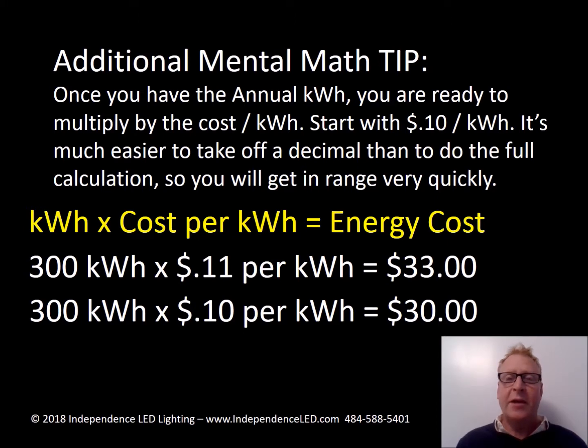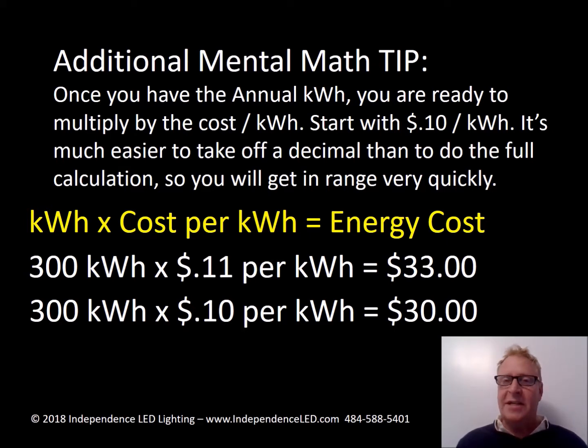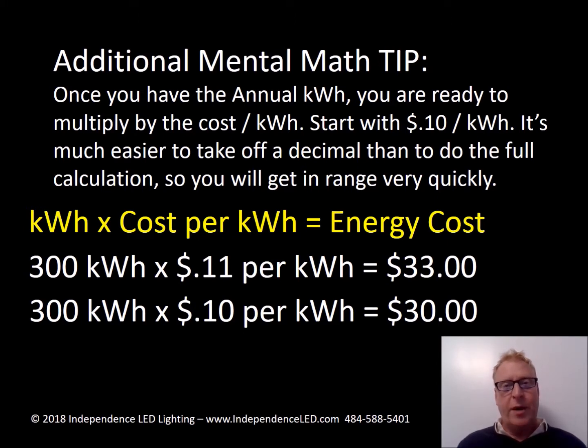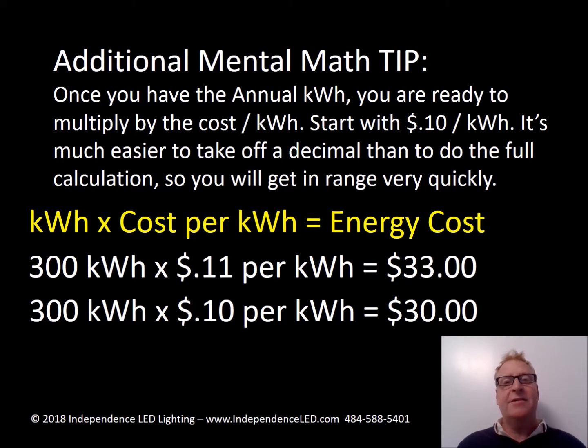Here's an additional mental math tip: once you have the annual kilowatt hours, you're now ready to multiply by the cost per unit. If you start with 10 cents per kilowatt hour, it's much easier to move the decimal than to do the full calculation, so you will get in range very quickly. In this case, with 300 kilowatt hours at 11 cents it's $33, or at 10 cents it's $30. That gives you the range, and once you have the exact kilowatt cost for the facility or your client, you can run the numbers — but at least you've got the right order of magnitude.